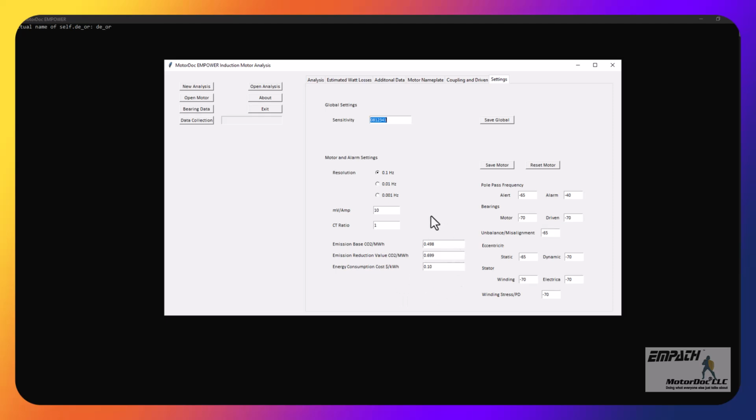This would be for data related to energy and emissions for the auto analysis. And what's kind of cool about this section, including setting the alarm limits, is there are two things. First is, this is the default alarm limit. The software then makes adjustments based upon where the noise floor is, so that you maintain a constant; it reduces false positives and false negatives, basically.